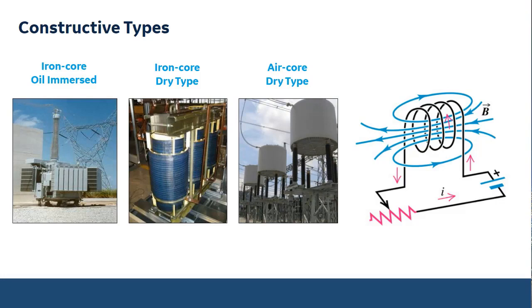And this path basically keeps the magnetic field inside of it. So it creates a high permeability, low impedance path for the magnetic field. So that's the first difference. Constructively speaking, iron core reactors are much heavier and larger than the dry type air core, but there are reasons for having the iron core. So the second thing is oil.